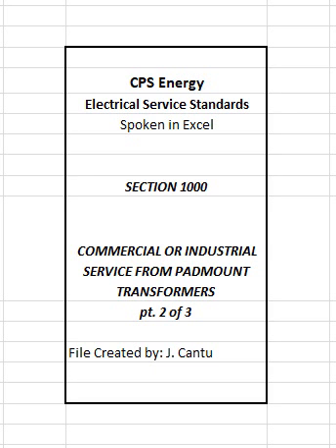2. Tap box shall be connected to side of transformer at secondary compartment with a 3-foot-long wireway furnished by customer, refer to Table 1002 for sizing of wireway. 3. Wireway must be installed 3 inches above the transformer slab and centered on the side panel of the transformer's secondary compartment. CPS Energy will make the necessary opening into transformer secondary compartment.